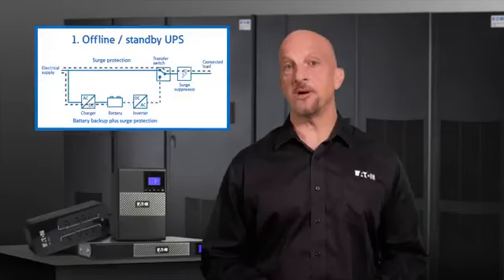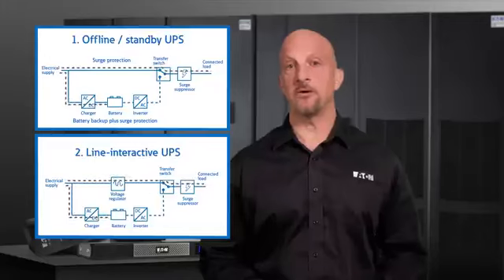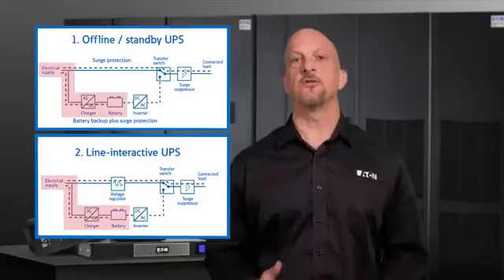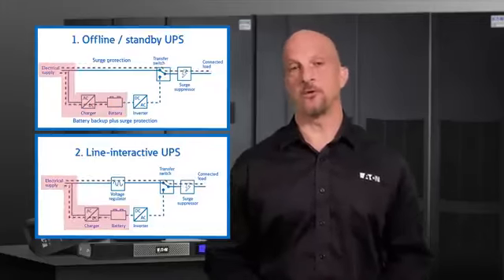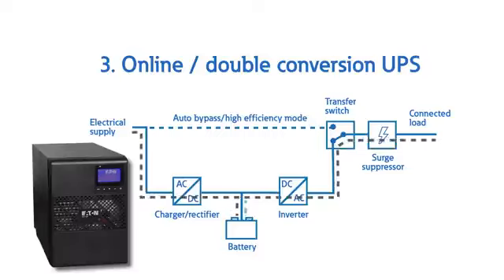Note that both the standby and line interactive UPS batteries are charged as needed from the normal utility source when it's available. Finally, the online or double conversion UPS is a significantly different design, especially on the front end or the input to the UPS.